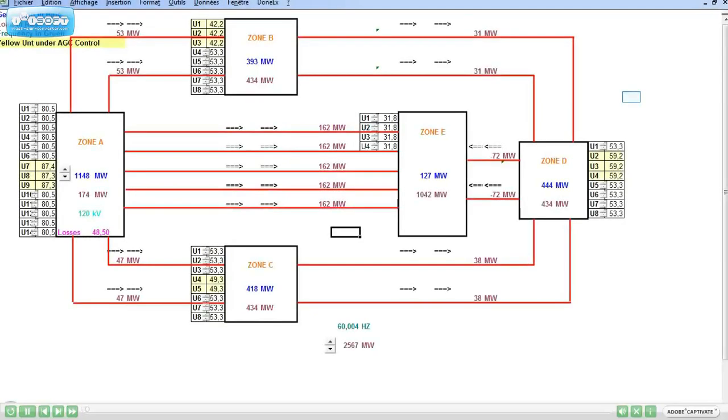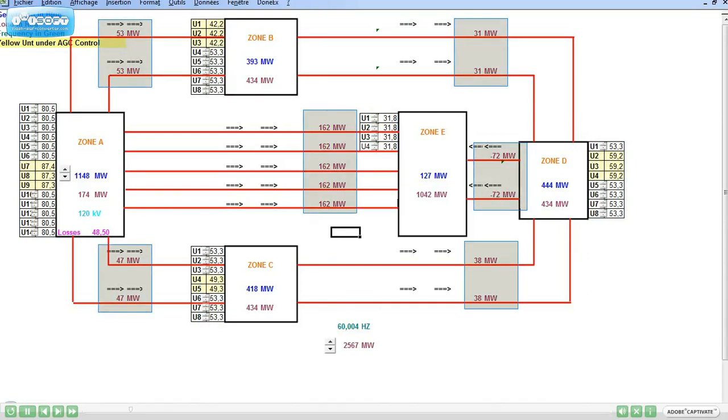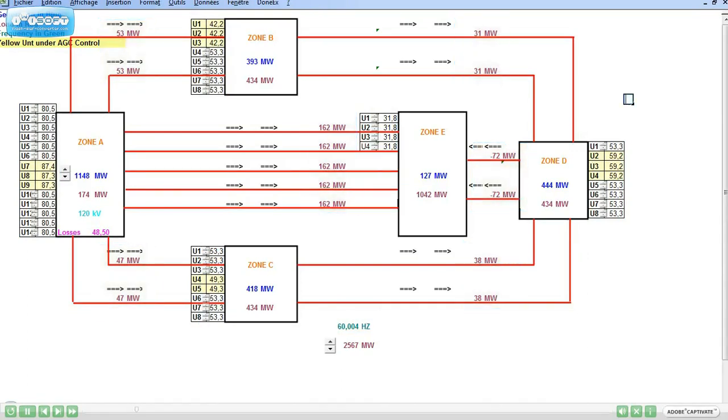Welcome to the Transmission Line Relief Simulator. With this simulator, users have to increase the load, and note the change in loading of the generating units with 5% speed droop setting. They also have to note the change in frequency, and the change on the line's loading. As a result of these actions, users will have to redispatch to remove overloads on lines and/or generators, and also reconfigure the grid system to bring the load on this grid system to a minimum of 4,000 megawatts.